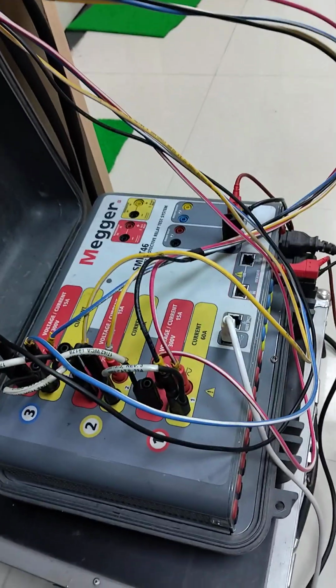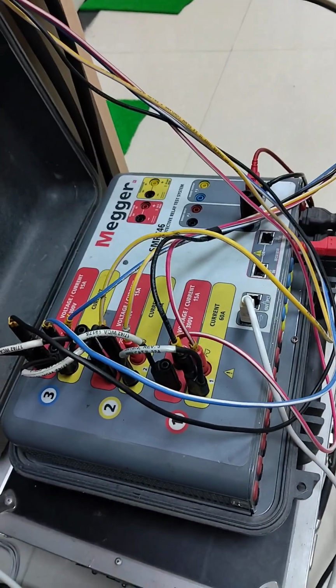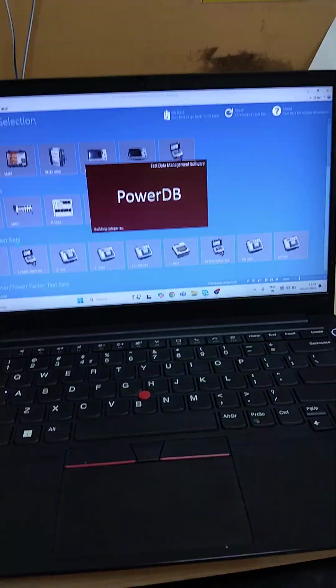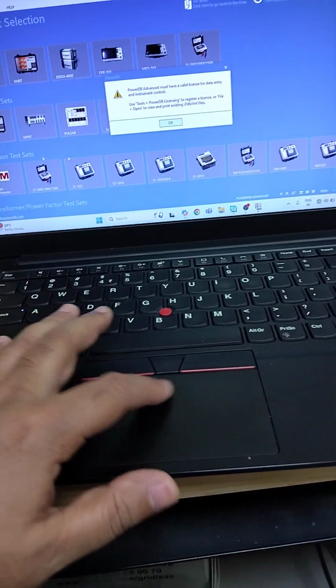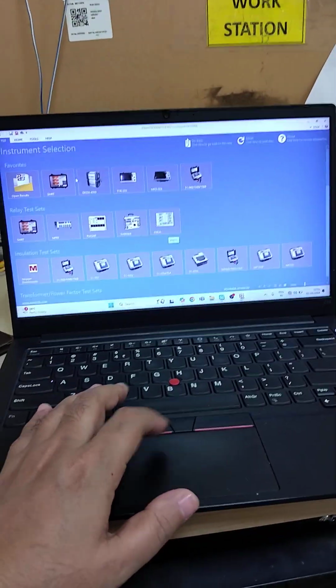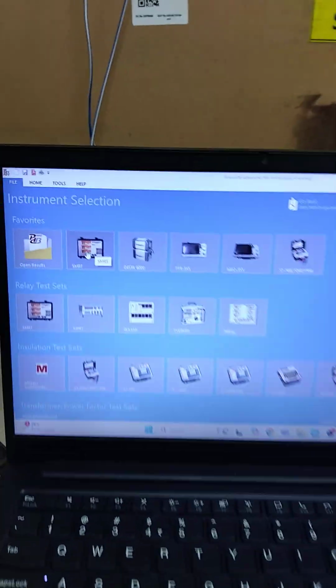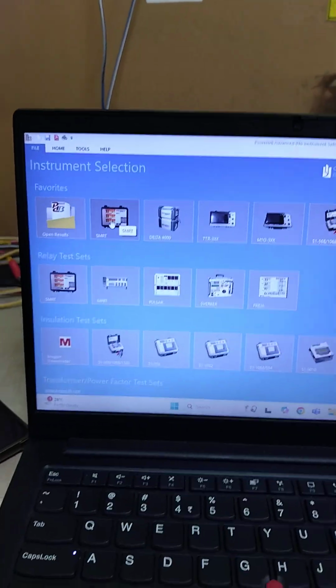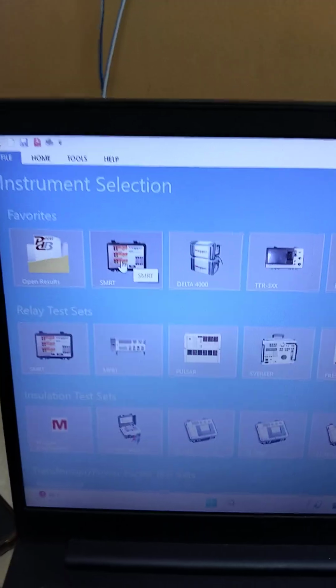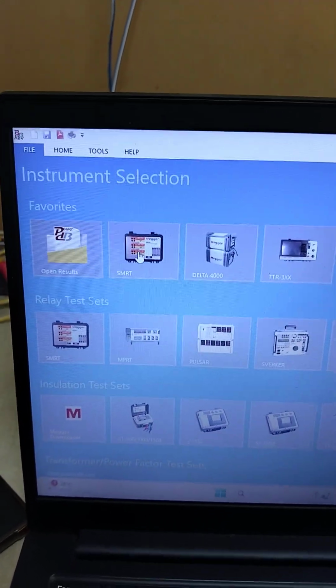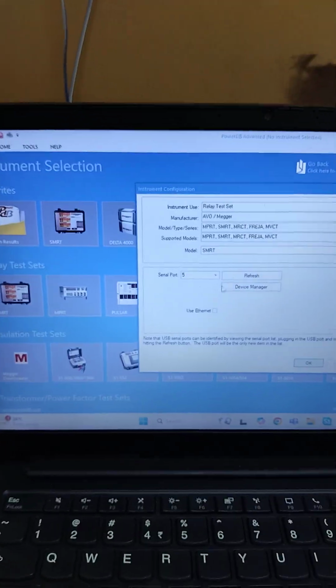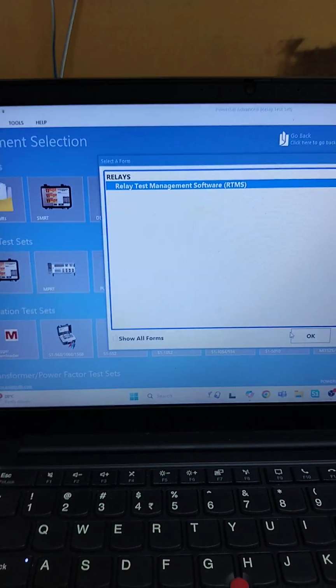So open PowerDB and we'll connect the laptop with PowerDB and the kit will be connected, and then we'll enable the power supply to switch on the relay, and then we'll inject the current to test the differential protection with the settings that we entered in the relay, and check the SMRT tab, update the port here, connect, OK.